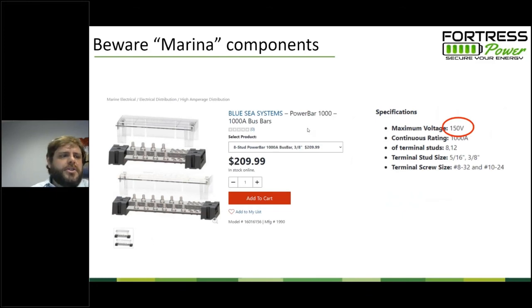One item that I would caution you about is buying bus bars from the marina industry. If you're looking for cheap disconnects, cheap overcurrent protection, cheap ways to parallel batteries together, there's other markets that have these problems. And so you might find something that looks like it'll fit the bill. You have to make sure that the voltage ratings are also correct. Kind of the opposite of what we had earlier with battery inverters and batteries giving you voltage ratings, but you having to calculate the DC side amperage on your own.